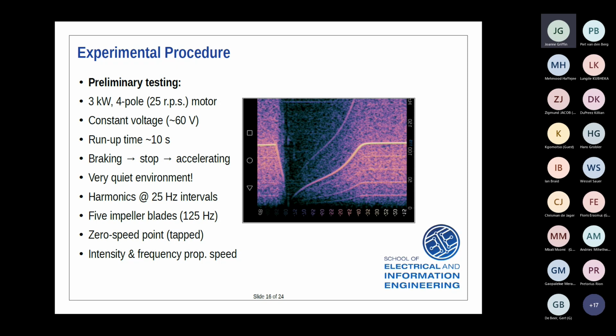You can see the braking region is actually very short here, very short duration. You can see the acceleration time is quite long. So here, as I showed you right in the beginning, this emulates a speed versus time trace, and you can see the gradient, which is acceleration. You can see it accelerates quite quickly in the beginning, slows down a bit, and then here, as we reach a pull-up torque, you can see the gradient is climbing very steeply. So this is typical. Just by looking at this, you can see it's already a single cage machine.